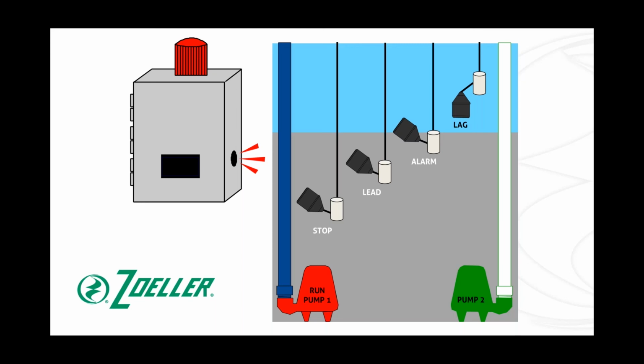So what's happened here? Well, pump 1 is running. It's not keeping up with the flow. Our alarm has been activated. So now our audible and visible alarms are both on. Notice pump 2 has not been called into action yet. With a float setup such as this, there's going to be a period of time where you would have an alarm situation. This will alert the user that something might not be right, and it will give them a little bit of time to try to determine what's going on or what to do.